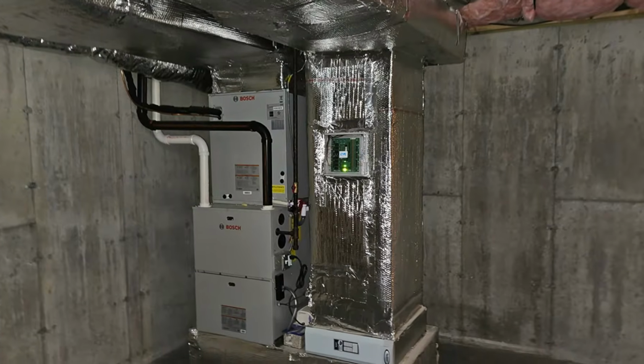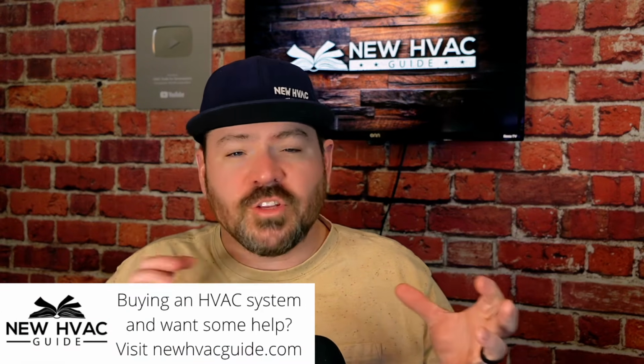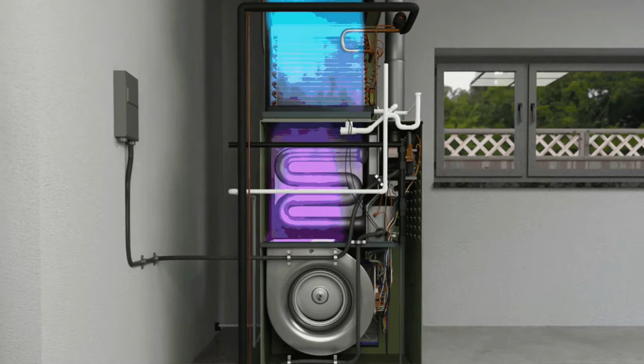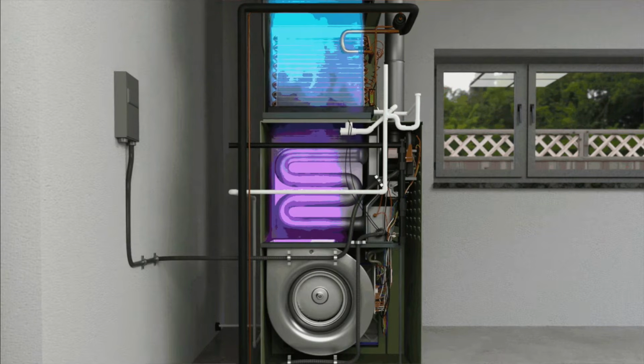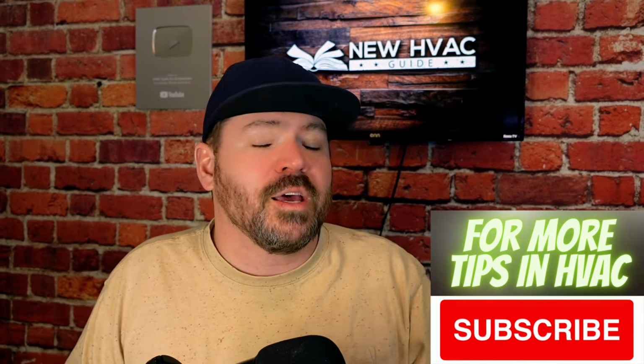Number one of the most common problems I see with furnace failures is the size of the ductwork connected to that furnace. In fact, I would go so far as to say that the majority of furnaces in our country have ductwork that is undersized. And as we move into a realm where most people are switching to today's technologies, where the furnace had a PSC motor for years and years, and now we're reusing ductwork and installing a furnace with a variable speed motor or possibly a constant torque ECM motor, regardless of what kind of motor it is, PSC motors by default would slow down and continue to operate when the ductwork is undersized and it has high static pressures. But today's furnaces with variable speed motors, because of the way the technology works, will actually be louder than that old furnace. The airflow through there, because simply the ductwork is undersized.